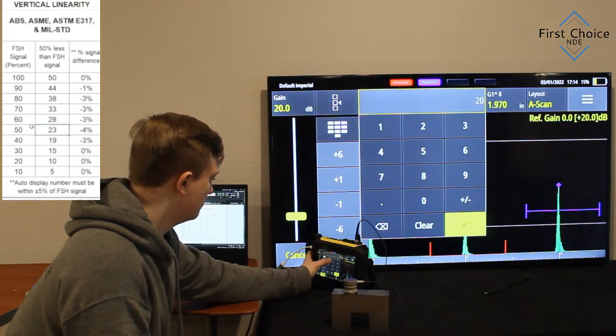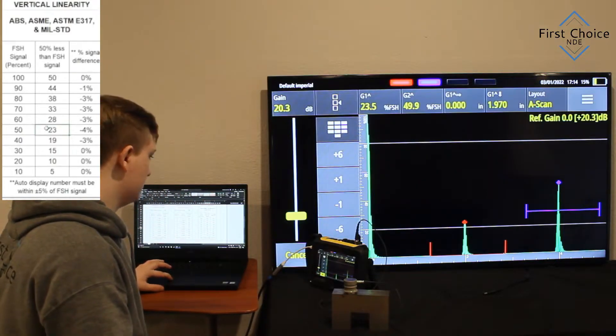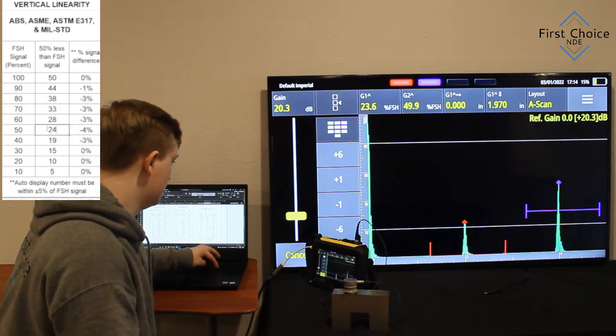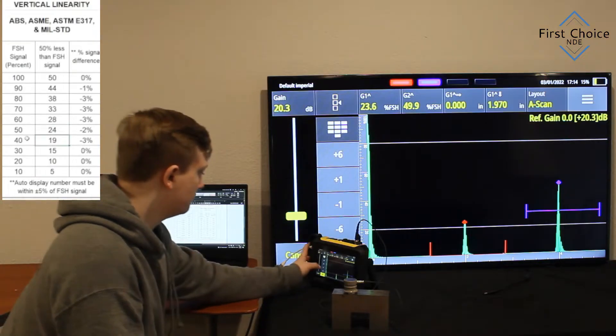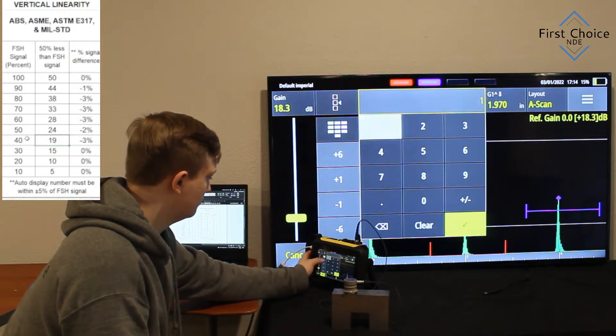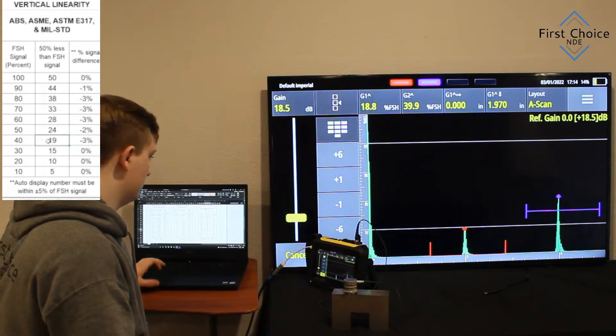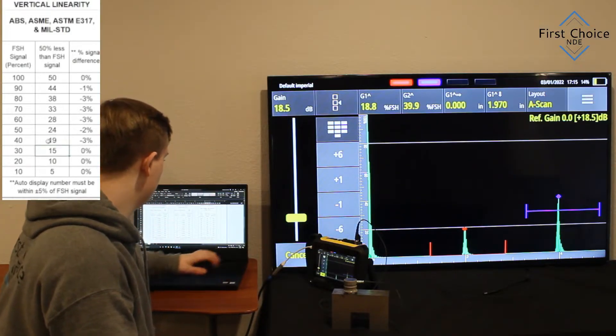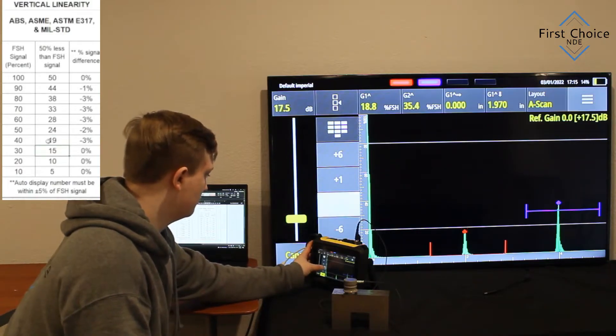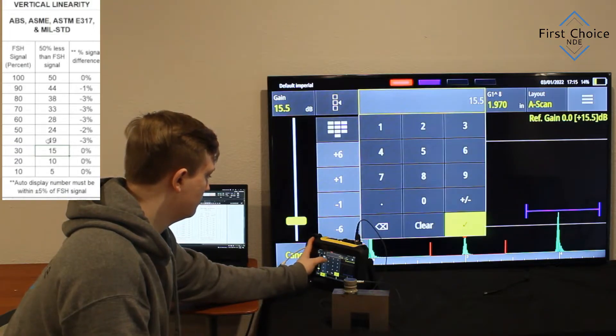Alright, so we did 60% on the right signal, and that ended up being 28%. Another minus 3%. Looks like we have 50%, 49.9. Signal on the left is 23.6 roundup, 24. That's a minus 2% differential. Lowering the dB again, 40% on the right signal, 19% on the left one, that's a minus 3%. So we're still, so far, every category is within tolerance.